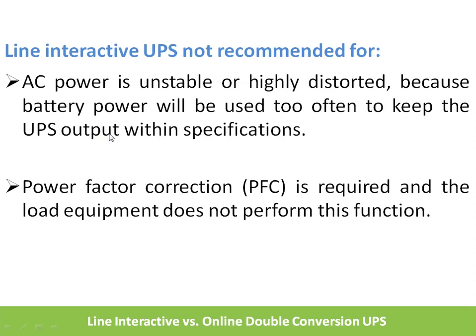This UPS topology is not recommended whenever the AC power is unstable, that is, if it is frequently going on and off, or if the voltage range is beyond the AVR specification, or it is highly distorted, meaning a high amount of noise is present. In all these cases this topology is not preferred because it frequently goes to battery mode, and the number of battery charge and discharge cycles increases, which decreases the battery life.